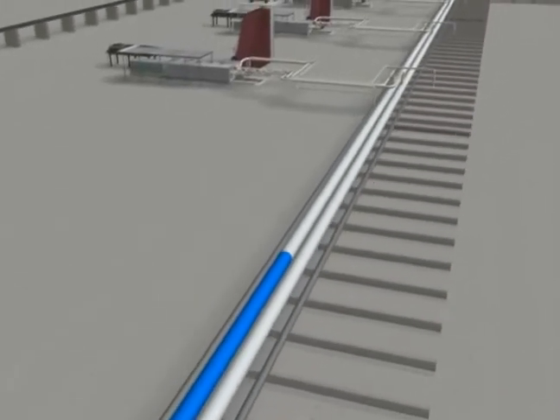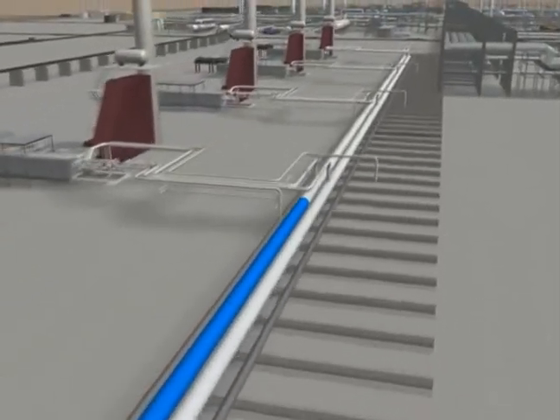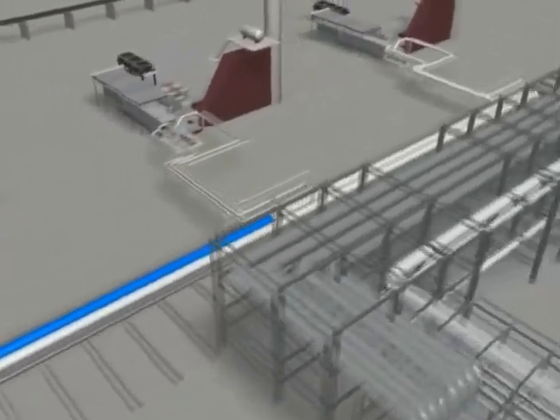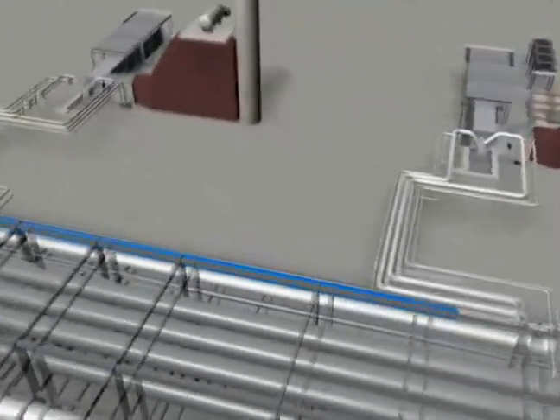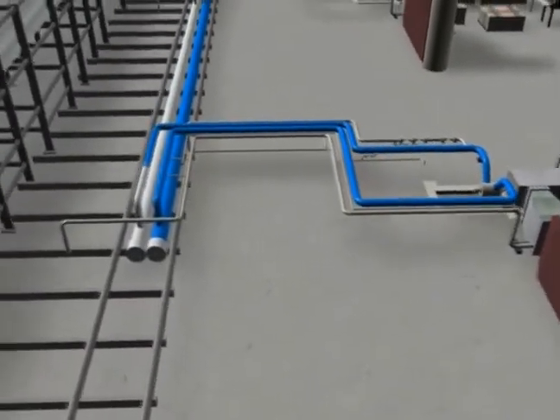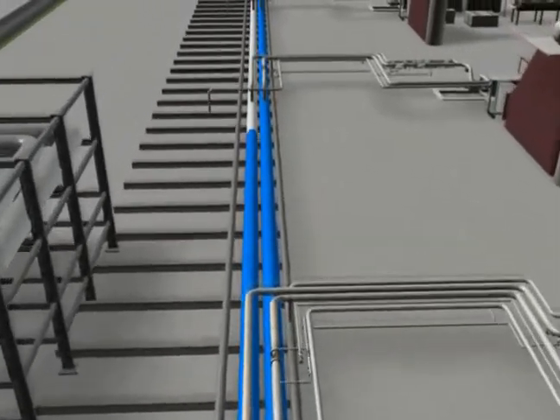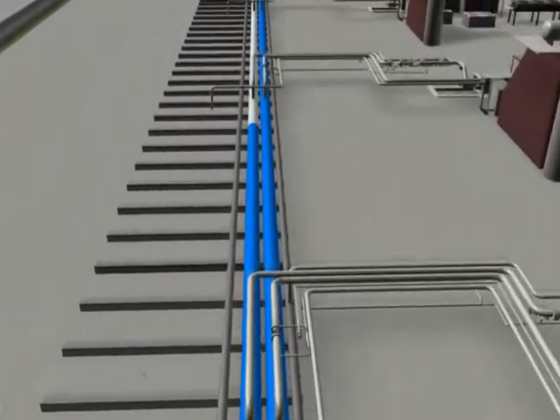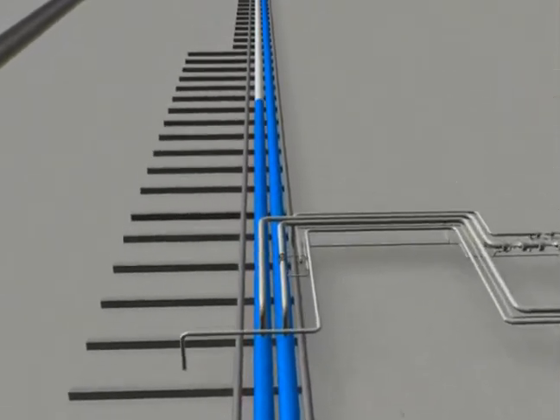Water injection plant will house a 13.8 kV substation, process interface building, instrument air system, fire water system, and team building and water injection facilities. To achieve 2,850 psig for the 2.14 million barrels per day of treated seawater coming from the Andar Water Injection Plant, the Khurais Water Injection Plant will utilize 5 turbine-driven injection pumps, each delivering a total of 12,500 gallons per minute to both Khurais and Abu Jifan fields.